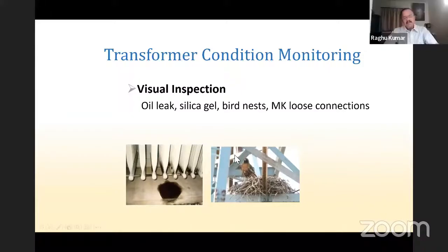Next is a bird nest. This looks like a minor issue. No, it's not a minor issue. See what happens with open bushing transformers. A bird nest comes up, and then the bird is not the problem. There are cats coming looking for these birds. The cats jump over the transformer and cause a direct short circuit. And this has also caused tripping of the transformers. And the loose connections inside the marshalling kiosk are also a major headache. The control cables can get loose and give a short circuit, and without a fault, the transformer can trip.